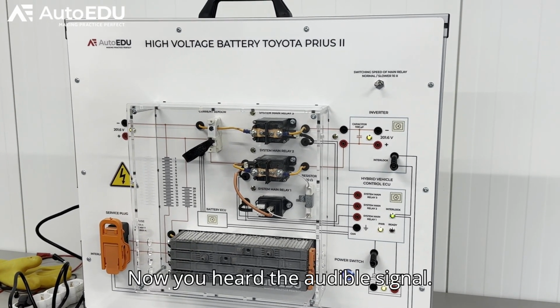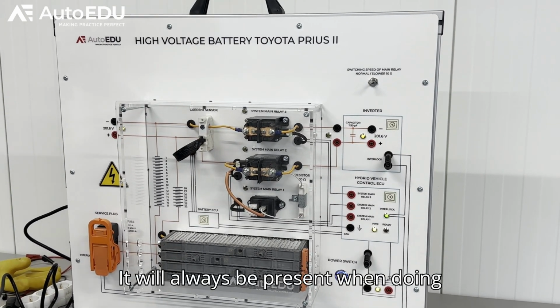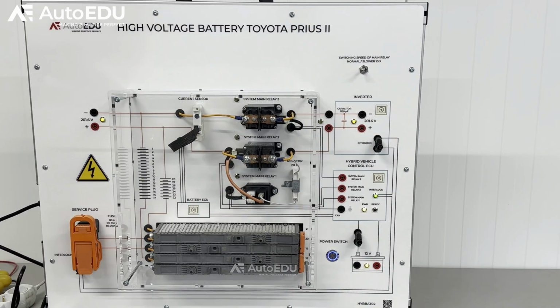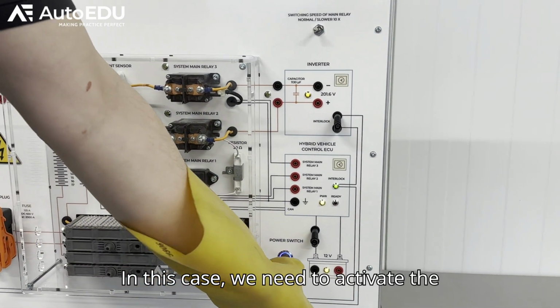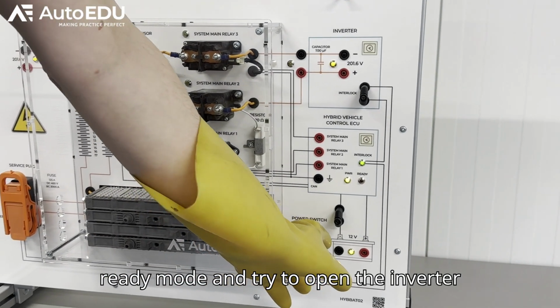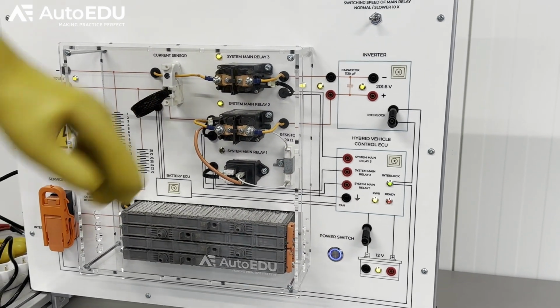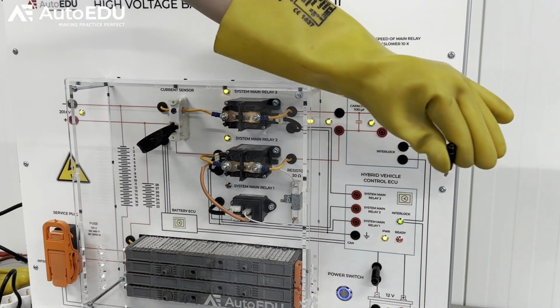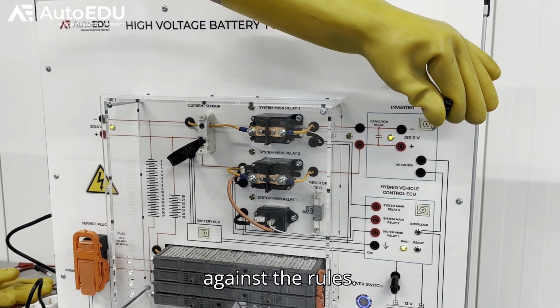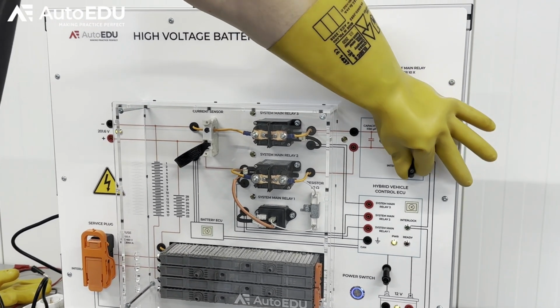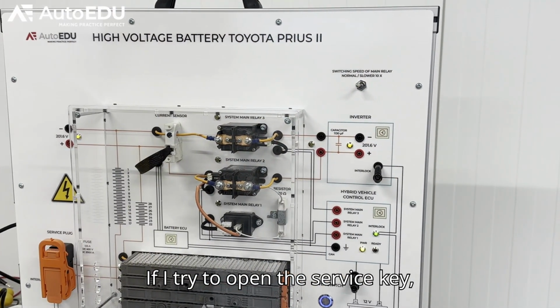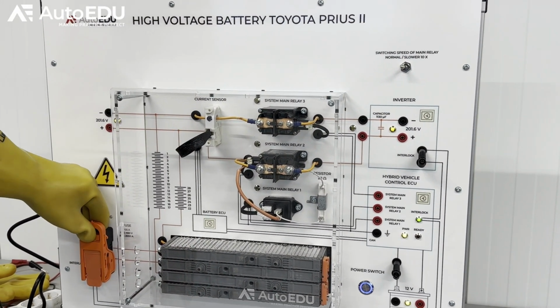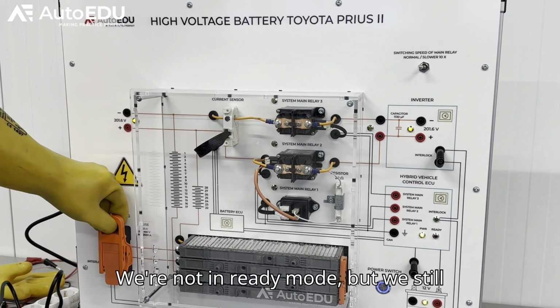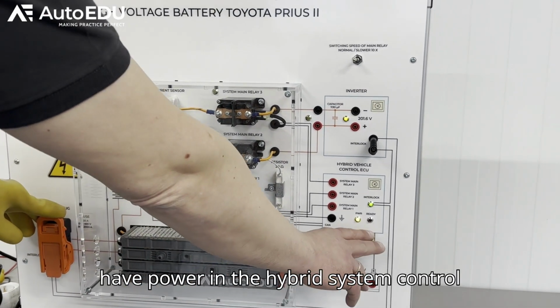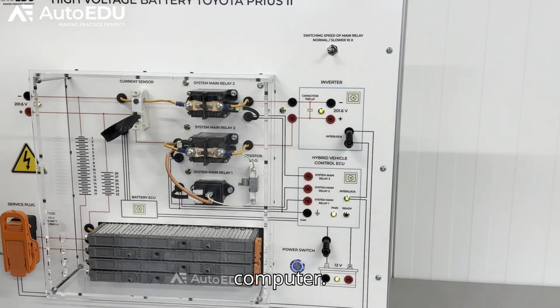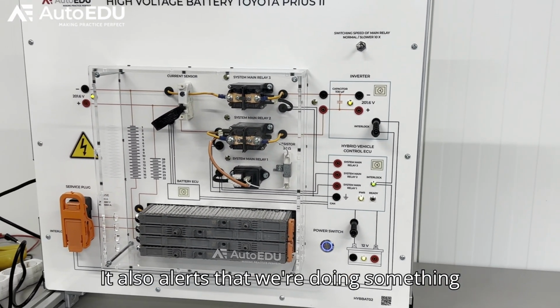Now, you heard the audible signal. It will always be present when doing something against the rules. In this case, we need to activate the ready mode and try to open the inverter cover. It alerts us that we did something wrong against the rules. If I try to open the service key, it also alerts. We're not in ready mode, but we still have power in the hybrid system control computer. It also alerts that we're doing something incorrect.